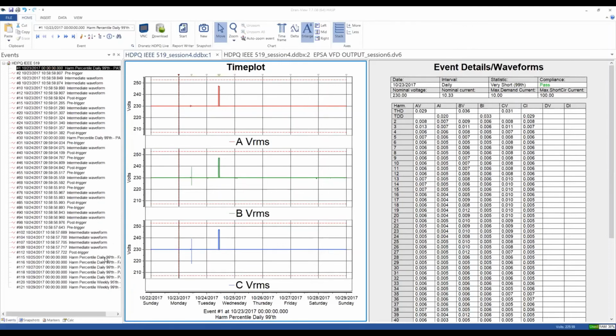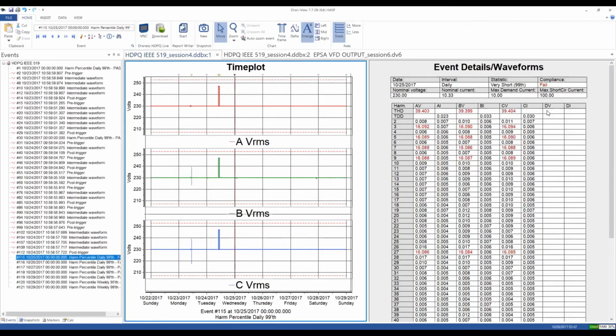If I look down here and select one of the ones towards the bottom, this is a fail report for a very short time harmonic. It's failing because of the THD, and these individual harmonics for voltage were out of the required limits. These are actually quite high for this particular application. For voltage harmonics, the allowable limits are certainly below 10%, 5-8%, something like that, depending upon the bus voltage. So you can see how DranView produces this information, which is basically just displaying this for you from the instruments. You'll see something very similar in the instrument itself.